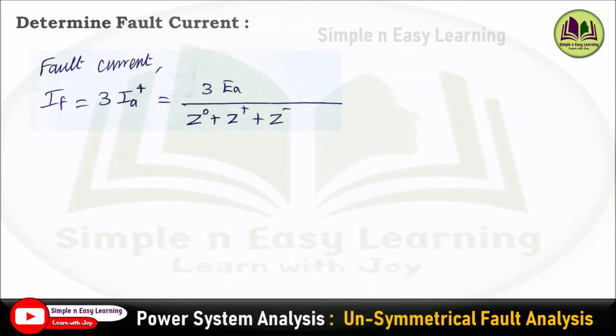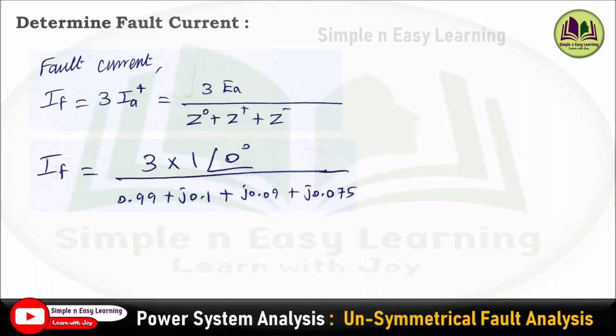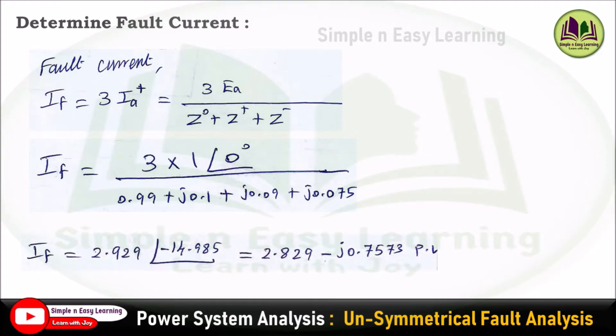Now determine the fault current. For a single line to ground fault: IF = 3×IA+ = 3×EA / (Z0 + Z+ + Z−). The induced EMF EA is not specified in the problem, so per unit value is taken as 1∠0°. Substituting Z0, Z+, and Z− values determined previously, IF = 2.929∠−14.985° or equivalently 2.829 − J0.7573 per unit.